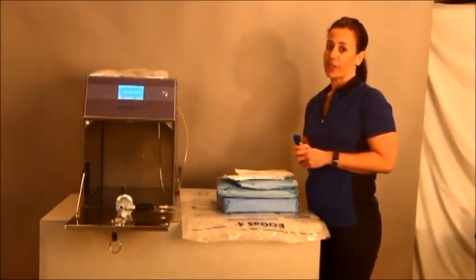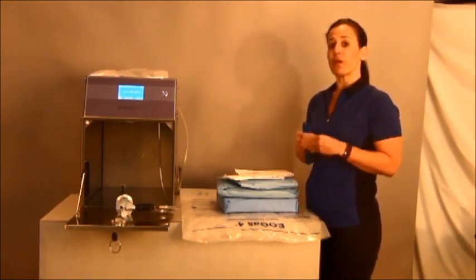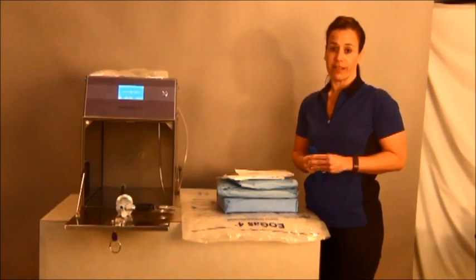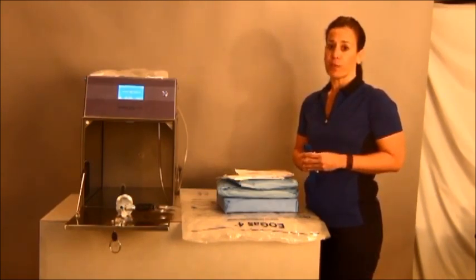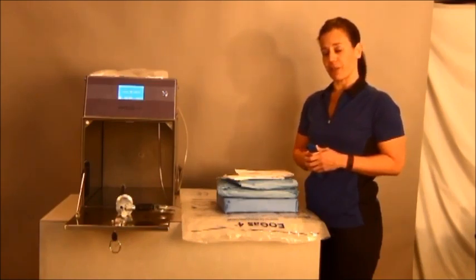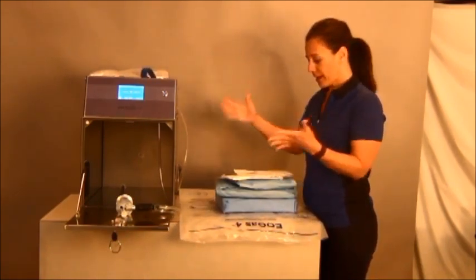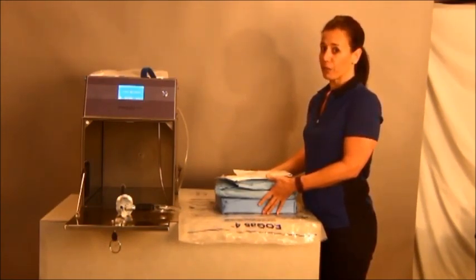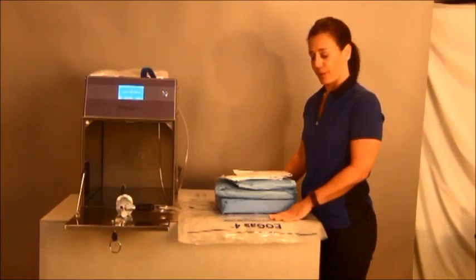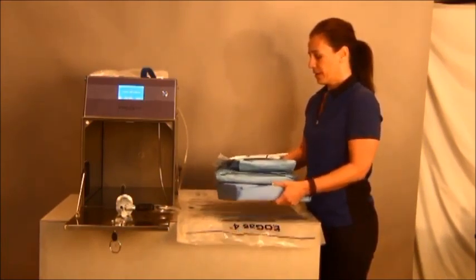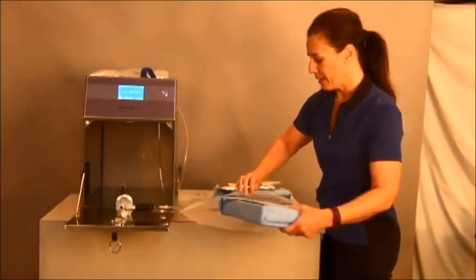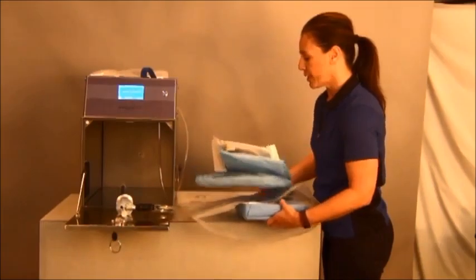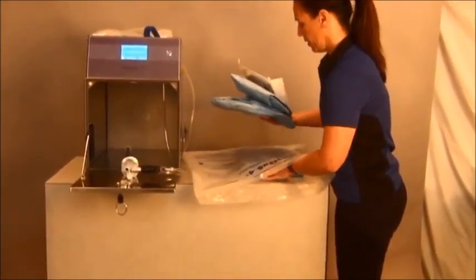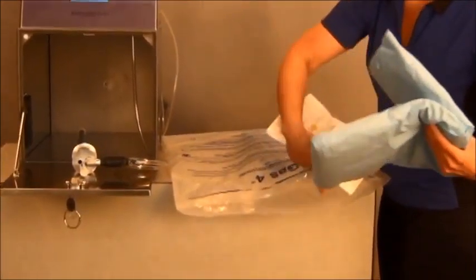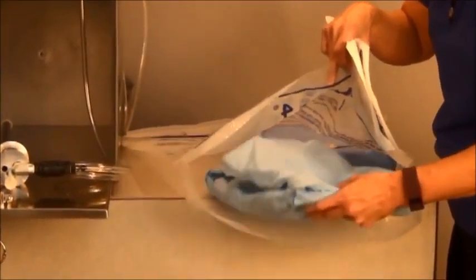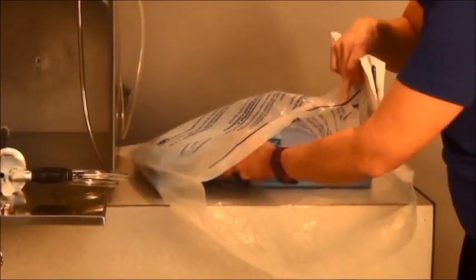The process of loading the sterilization liner bag is very important. You want to load the liner bag in the same fashion every single time you run a cycle. Uniformity is a very important process of the sterilization cycle. The items that you're going to be sterilizing have already been disassembled, washed, dried, and wrapped, and now are ready to put into the sterilization liner bag. You want to put your items in, starting off, moving them towards the center of the liner bag. Placing them loosely so the ethylene oxide can move throughout the liner bag and penetrate the items that you're going to be sterilizing.